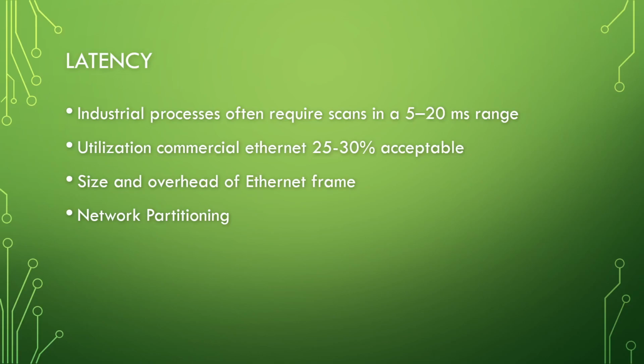If I plug into this Ethernet jack and you're connected from the business network to the industrial network, I can now talk to every one of your PLCs, which I've done here. I don't know what PLCs I was talking to. I think it's those on that robot. I don't know why, they shouldn't be on the network. One day I did a scan of our network from the STEM building, and all of a sudden there were 5 or 6 PLCs showing up that I was not expecting. What the hell are these things?